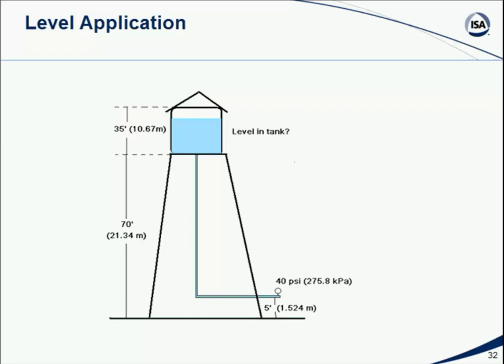Right? So the height of the tank in this particular case is going to be the pressure we measure divided by 0.433 times 1, or a pressure measurement of 40 psi over 0.433, which tells us that we're reading a column height of 92.378 feet of water. Right? Now that's feet of water up to the tank and where the level is in the tank. So we would know that we're 92 feet above, 5 feet above ground, or we're 97 feet up from ground level. So since the tank is 70 feet, we subtract 92 from that, and what we find out is that the level in the tank is 27.38 feet of water. Okay? In other words, it's about 78.22% full.